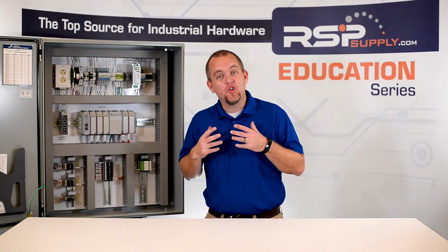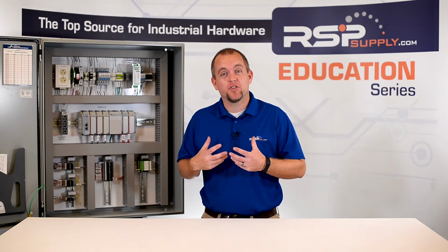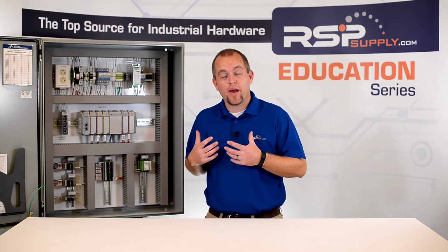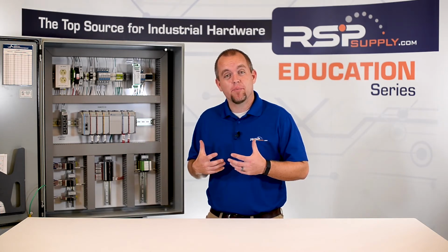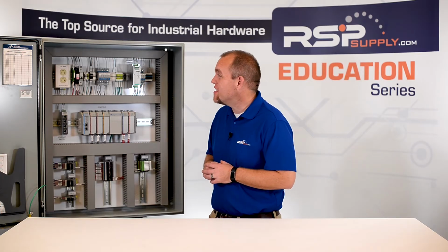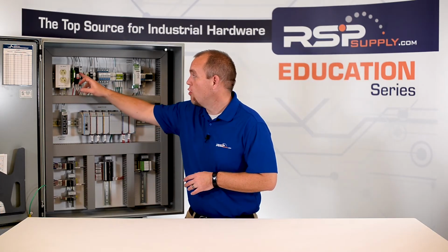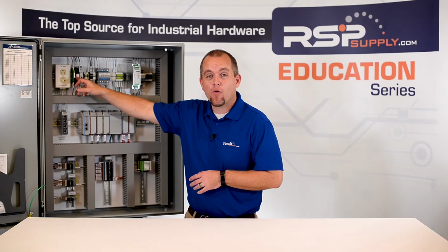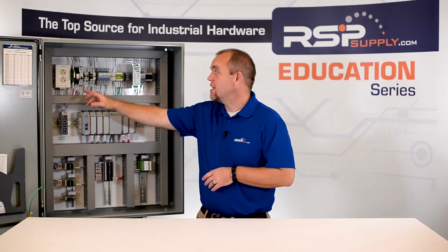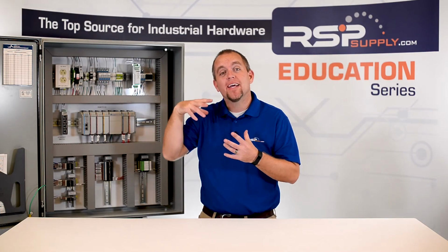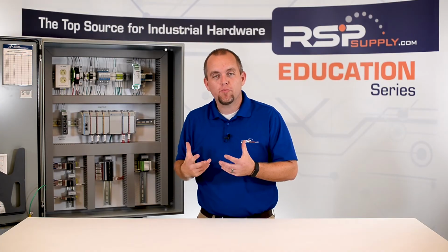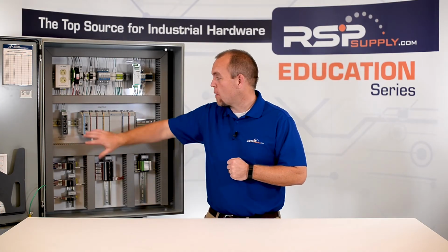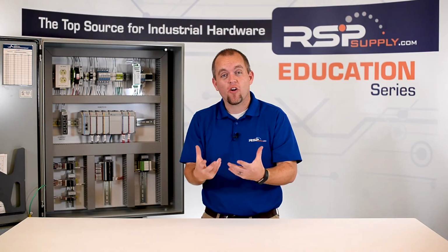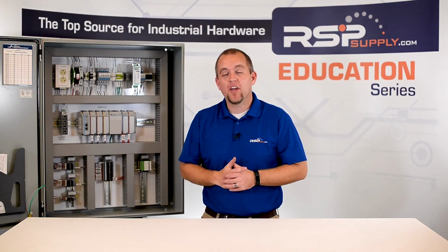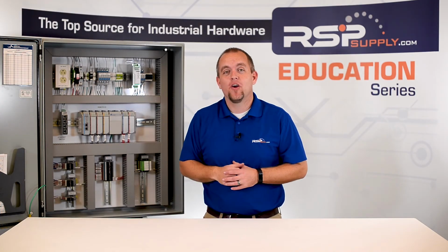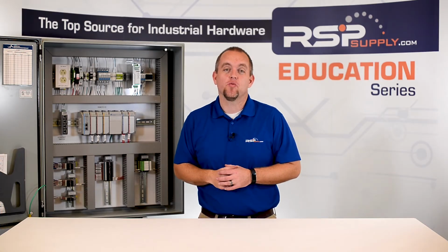In talking about the UPS and the fact that it allows us to continue to power the panel with a power failure because of the battery backup that it supplies, we have the ability to monitor power with what we refer to as a power fail relay. This relay monitors the power coming into the panel. If we lose power, it sends a message to our PLC saying that we no longer have power. However, we cannot use this power fail relay without also using a UPS.